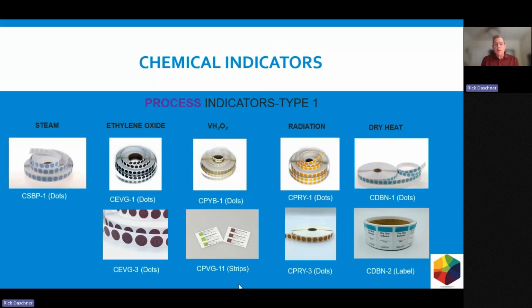So what does True Indicating offer? There in front of you is the list of all the process type 1 indicators that we offer. Now, type 1 indicators, as I mentioned, are indicators that say, yes, it was processed, or no, it wasn't. And you'll see we've got steam dots, which are usually just stuck on the outside of something, or can be put inside. Ethylene oxide, the plasma or hydrogen peroxide, the radiation indicators, and dry heat.